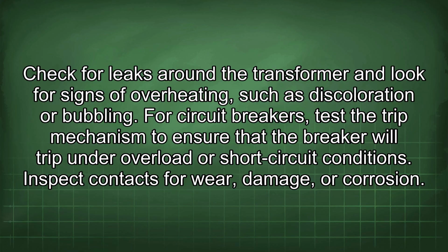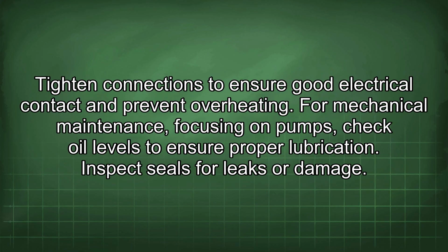For circuit breakers, test the trip mechanism to ensure that the breaker will trip under overload or short circuit conditions. Inspect contacts for wear, damage, or corrosion. Tighten connections to ensure good electrical contact and prevent overheating.